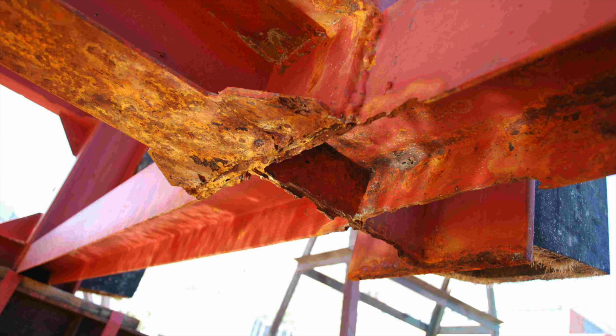This was quite graphically demonstrated because we took a walk down there once when it was back in the water, and we wanted to see what earthing arrangement they had. They just had a cable coming out from the workshop across the quay, with almost like a vice clamp onto this pontoon. And we said, no, this is not adequate. You've got to get a really good cable and a really good connection. Otherwise, you're going to get the stray current corrosion.